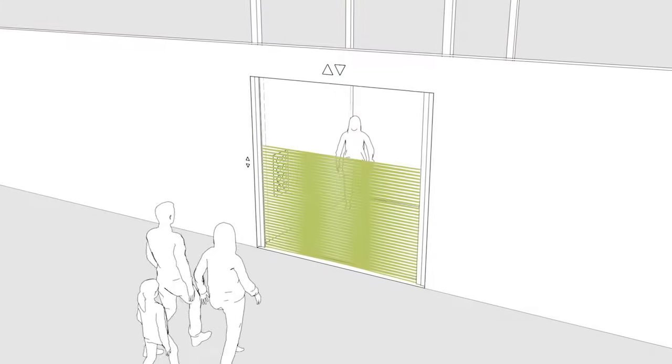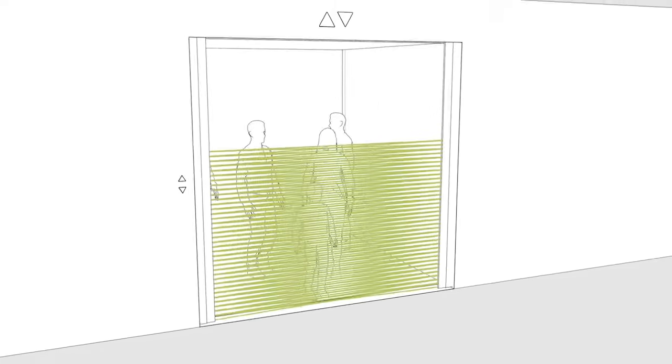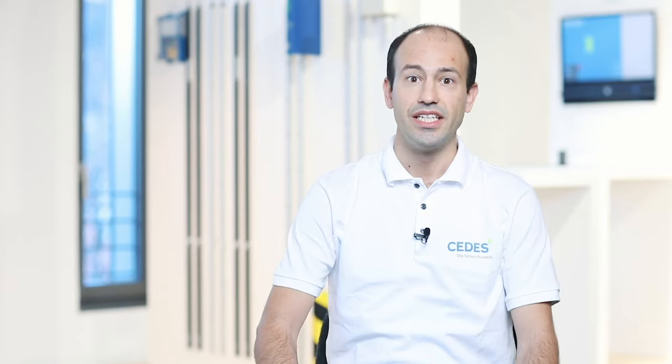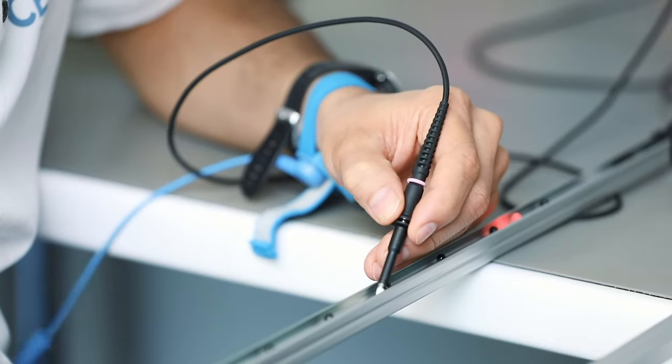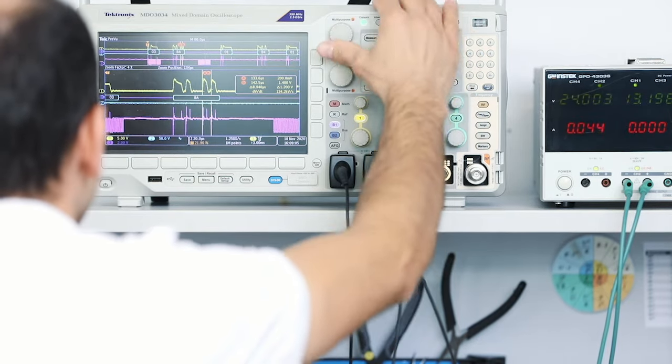The Capsafe 2D light curtain consists of a transmitter and receiver that have a defined field of infrared light beams used to detect the presence of objects in the path of the elevator cab doors. The Capsafe 2D detection field is made up of criss-cross beams that remain operational from full open to full door closure. In addition to fulfilling the code requirements, the transmitter and receiver are electrically synchronized to provide robust performance against infrared interference devices and for ambient sunlight immunity.